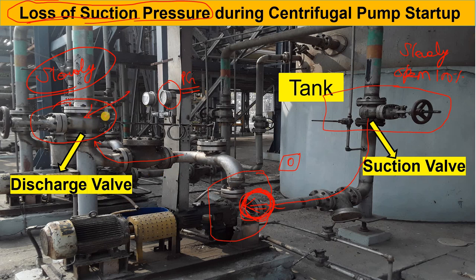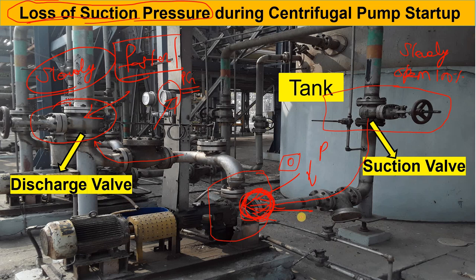That's why we say: whenever you are opening the discharge valve, open it slowly. If you open this valve faster or 100% at once, the suction side pressure will drop, which you can monitor from the PG. When this pressure goes below the vapor pressure of water at that temperature, boiling will occur, and because of that boiling, cavitation will occur. This is a very dangerous phenomenon for the pump — we have already covered topics about centrifugal pumps and cavitation, please watch those videos.